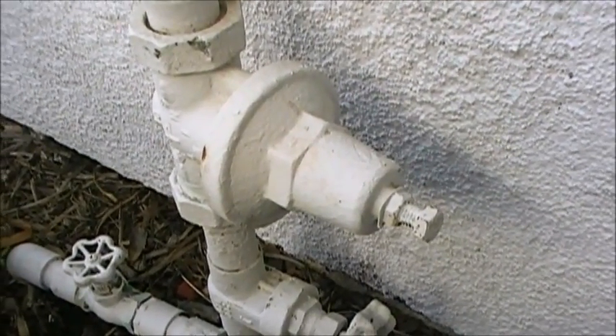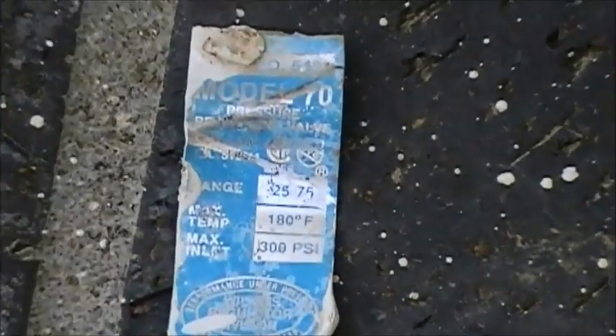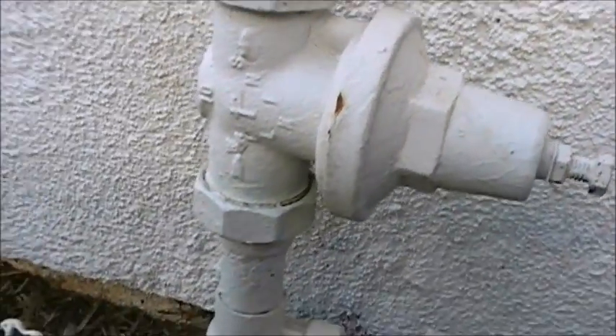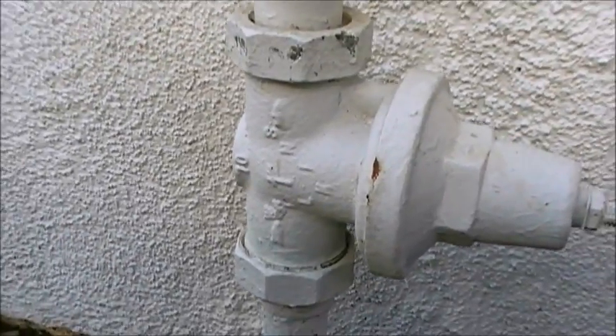The inspector said it was running around 100 to 120 PSI. It's a Model 70 from Wilkins, and I got one with similar specs. I was lucky enough to take a picture of its size — it's a one-inch pipe, or one-inch size pressure regulator.